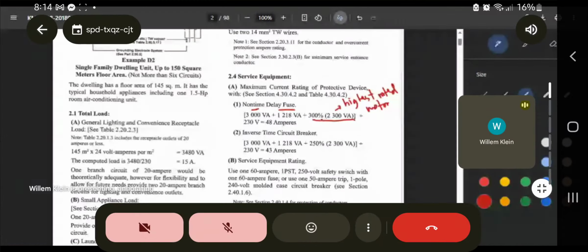So that's VA, or your power. So that's your total power, with your highest rated motor times 300% divided by your supply voltage. In this case, they use 230 volts. In your case, you can use 220 or 230 or even 240 if you like. Just make sure to be familiar with and know what supply voltage you used, because I might ask you when you present your output to me.